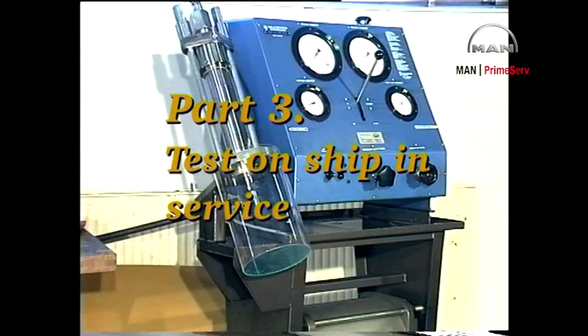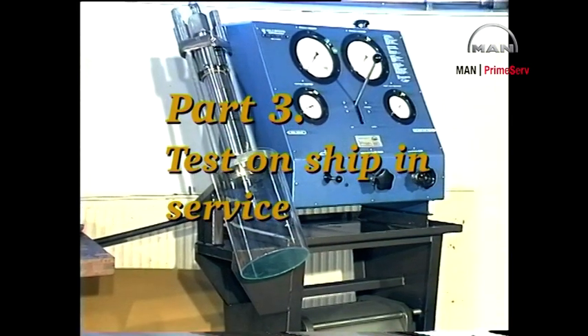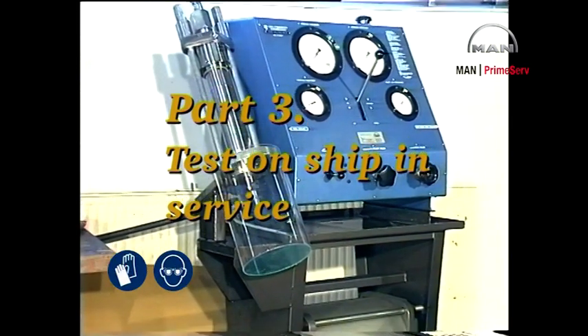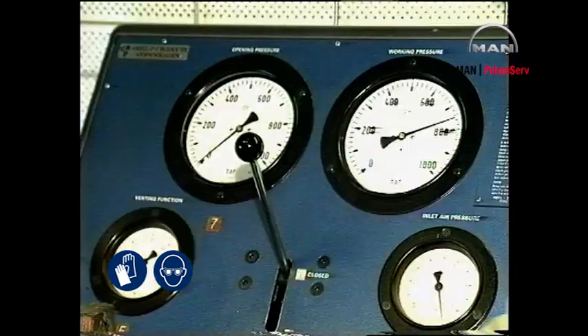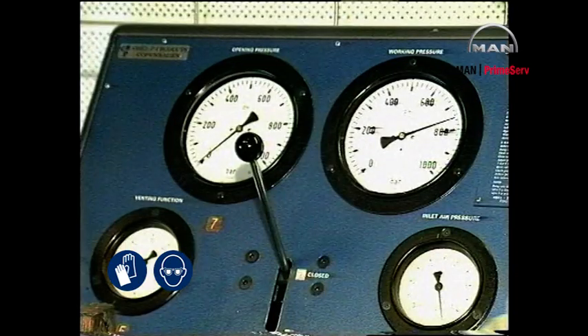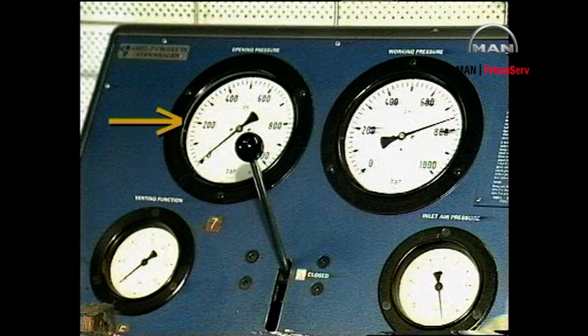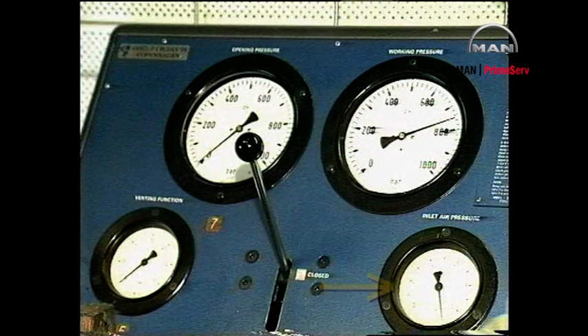Overhauled fuel valves or fuel valves taken from stock must be function tested before they are mounted in the cylinder cover. The pressure testing pump is equipped with pressure gauges for displaying opening pressure, working pressure, venting function and air inlet pressure.